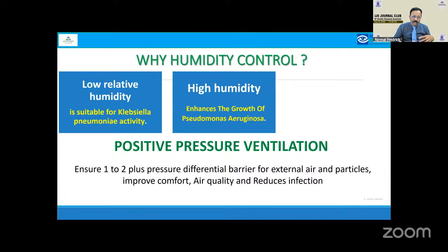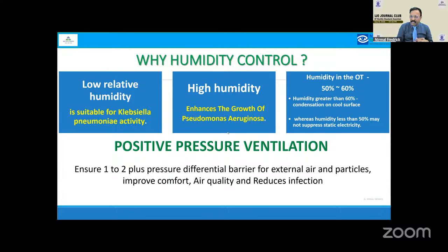Why humidity control? Low relative humidity is suitable for Klebsiella pneumoniae activity, while high humidity, a problem in our part of the world, enhances the growth of Pseudomonas, a common contaminant in cluster endophthalmitis. So we need to maintain humidity so it is not a potential ground for microorganisms to grow. Positive pressure ventilation ensures a 1 to 2 plus pressure differential so external air particles don't come in, forming a barrier.